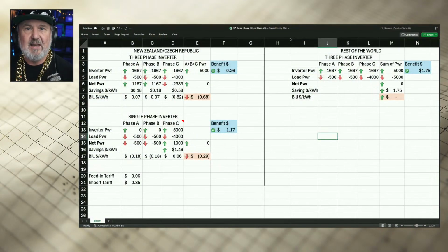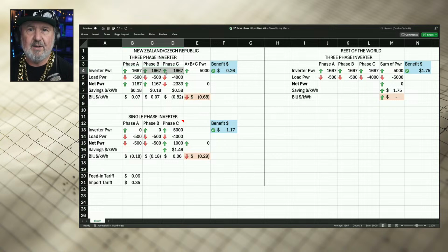So what you're looking at here is: on the left side is how things work in New Zealand and the Czech Republic when it comes to the value of solar as an offset to your consumption, whereas on the right-hand side is the rest of the world, which includes Australia of course. I've given 2 scenarios for New Zealand, both 3-phase installations, but one of them has a 3-phase inverter. You'll notice the power on the inverter - 5 kilowatts of generation at that moment - is being spread evenly across all three phases. That's what three-phase inverters do, it's called balanced generation: they push out that 5,000 watts equally as 1/3 on each phase. But the load power in the home is not necessarily balanced.